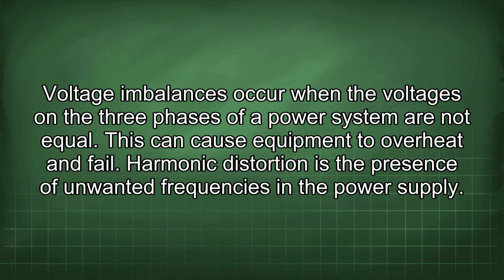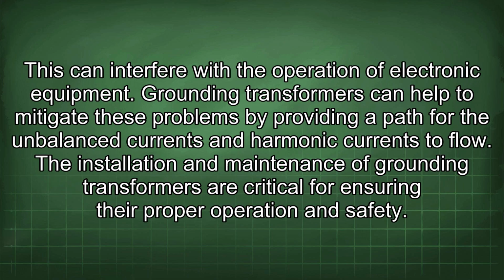Voltage imbalances occur when the voltages in the three phases of a power system are not equal. This can cause equipment to overheat and fail. Harmonic distortion is the presence of unwanted frequencies in the power supply. This can interfere with the operation of electronic equipment. Grounding transformers can help to mitigate these problems by providing a path for the unbalanced currents and harmonic currents to flow. The installation and maintenance of grounding transformers are critical for ensuring their proper operation and safety.